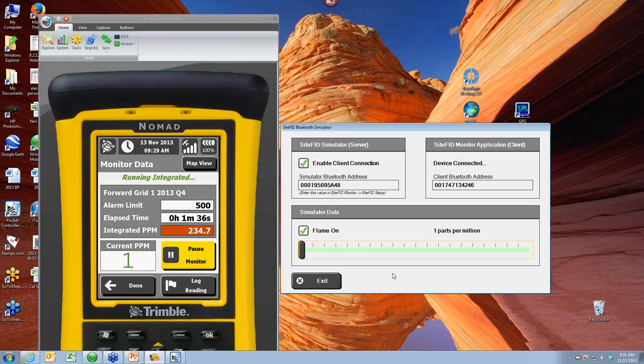Remember, the other thing going on is I'm capturing all this data in my integrated number. But let's say I hit 500 parts per million and I want to stop doing my integrated averaging, and do an instantaneous because I need to hit that hotspot and map it. All I need to do is hit pause monitor, then log reading, and take my wand over that hotspot.